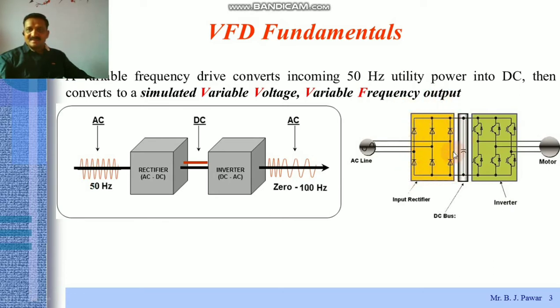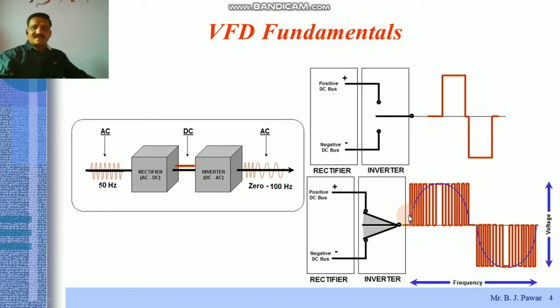Here the converter, that is rectifier, is shown as uncontrolled, that is by using diodes, so that the obtained DC is stored over here which is titled as a DC bus. And that DC bus voltage available is applied as an input to this three-phase inverter. Correct? So that was the simple mechanism of that VFD. We can call it as VVVFD, that is variable voltage variable frequency driver.